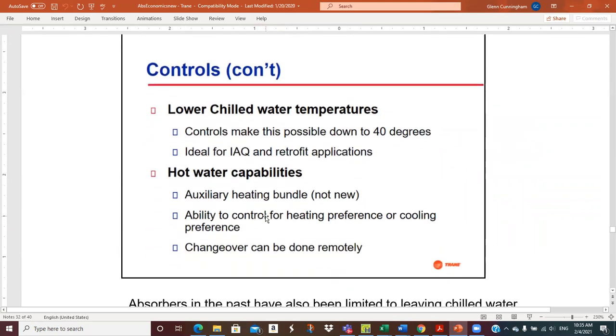Lower chilled water temperature controls make it possible to go down to 40 degrees, which is colder than the older units could go. Ideal for IAQ, indoor air quality, and retrofit applications. Hot water capabilities, we talked about that. We can get this auxiliary heating bundle. Ability to control for heating, preference, or cooling, and changeover can be done remotely. So you can change from a hot water priority to a chill water priority. It's very easy with the absorption.